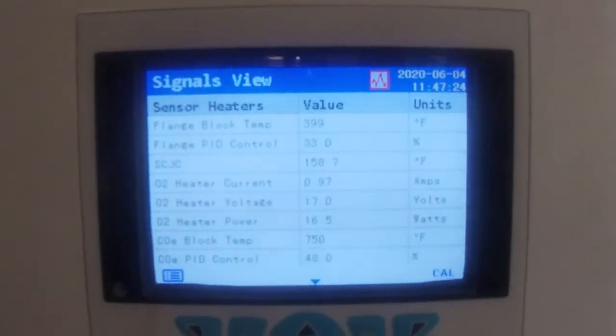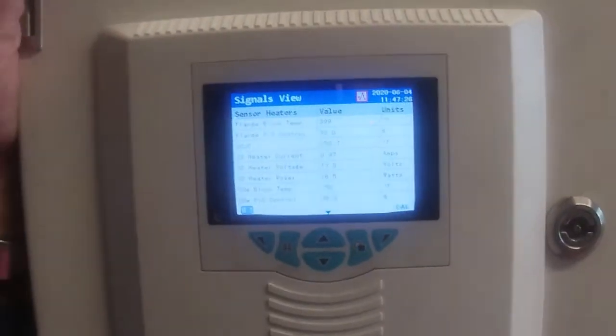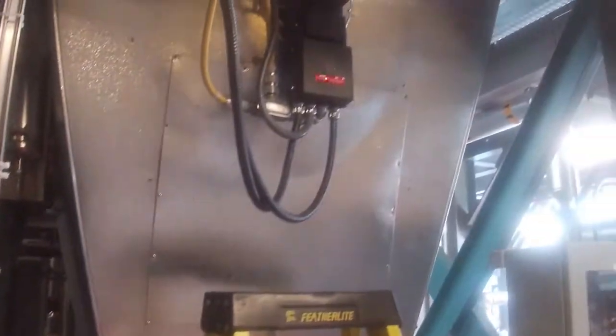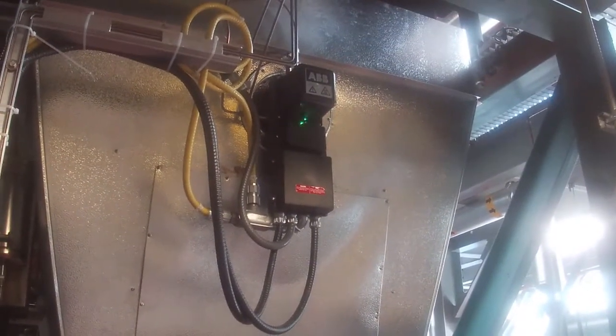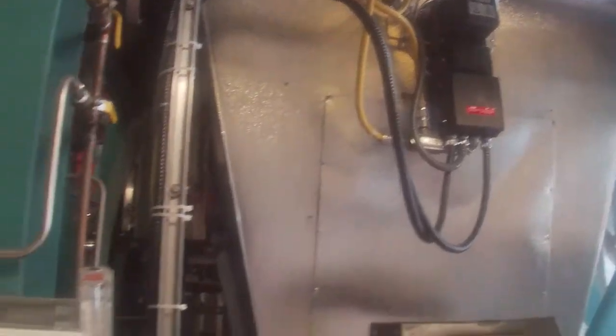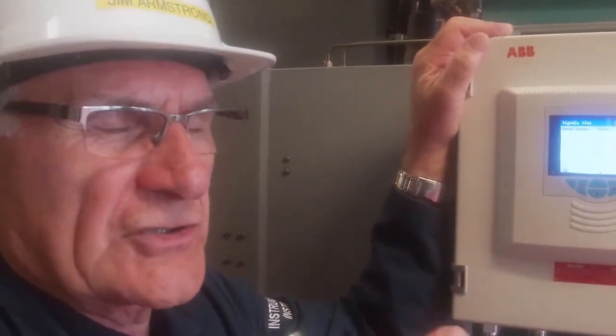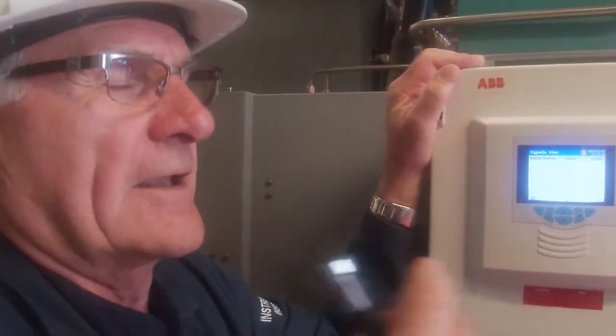Then we've got another thing that says SCJC, and that's the sensor head cold junction compensation. So there's a thermistor up in where all that electronics is up there. So up in where my laser's pointing right now, there's a thermistor actually in that section right there that is looking at what that cold junction compensation is, so it can give you the accurate temperature. You remember that with a thermocouple, you're looking at the difference between the cold junction and the hot junction, and it's that differential voltage which will tell you what the temperature is.